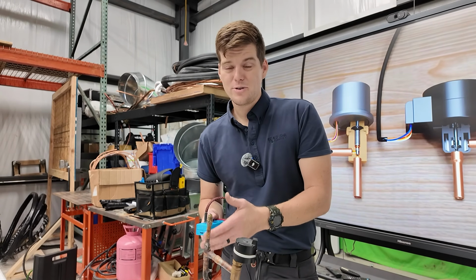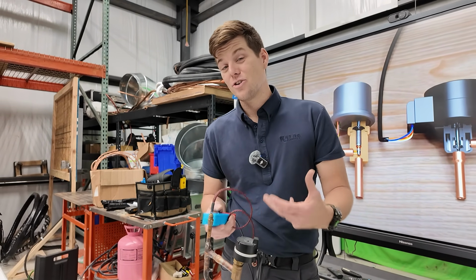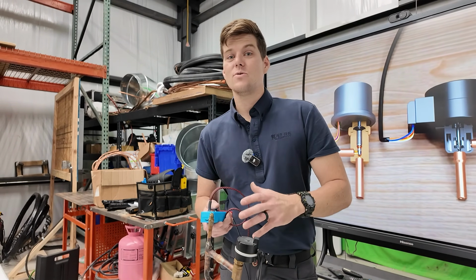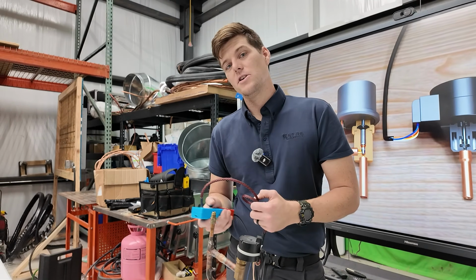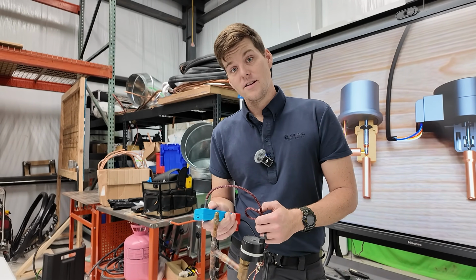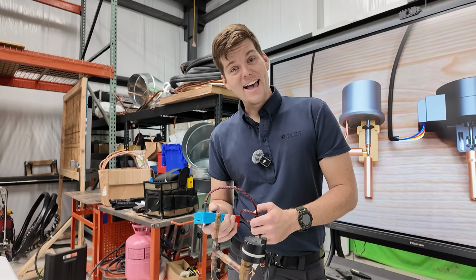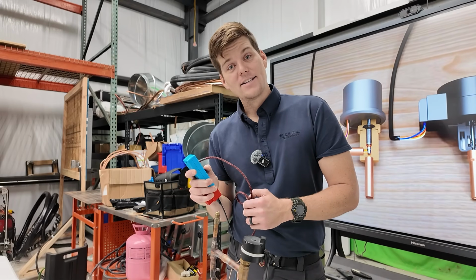There's no way to manually force the unit to open and close an expansion valve outside of turning it on and off. And even then, that doesn't work all the time. And so a tool like this can be extremely useful. So if I drive it pretty fast, drive it back down closed.